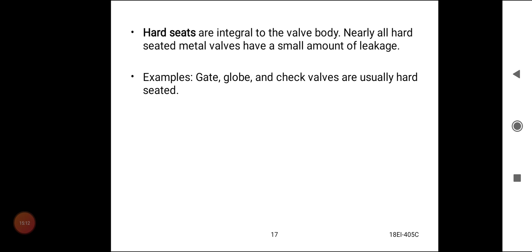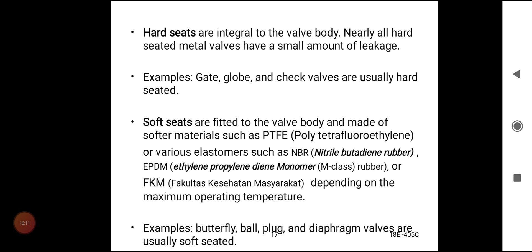Soft seats are fitted to the valve body and made of softer materials such as PTFE, polytetrafluoroethylene, or various elastomers such as NBR, nitrile butadiene rubber, EPDM, ethylene propylene diene monomer, or FKM, fluoroelastomer, depending on the maximum operating temperature. Butterfly, ball, plug and diaphragm valves are usually soft seated.